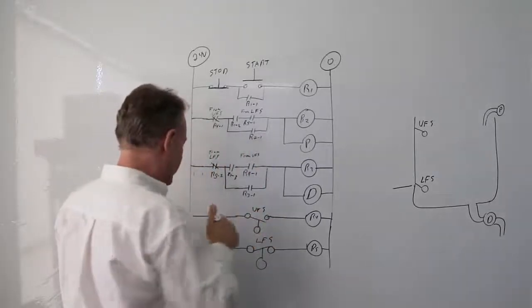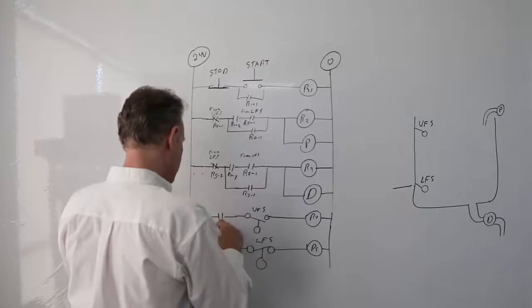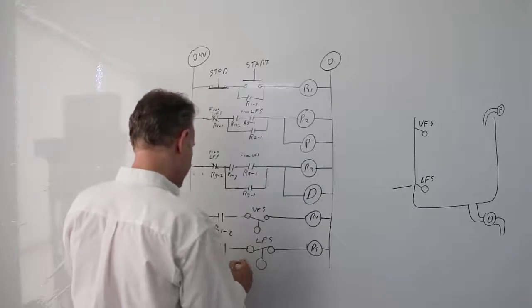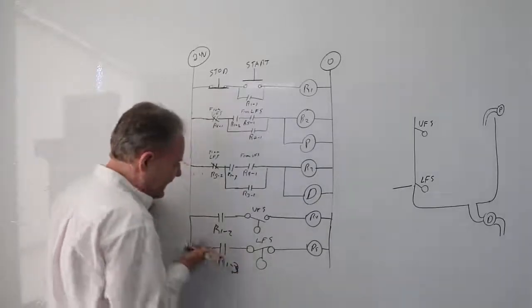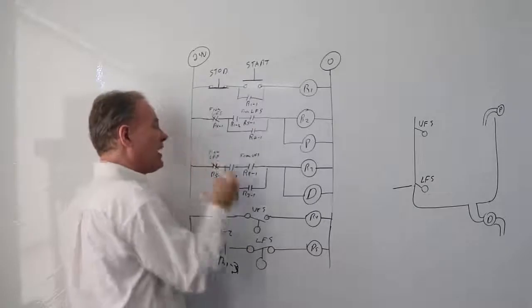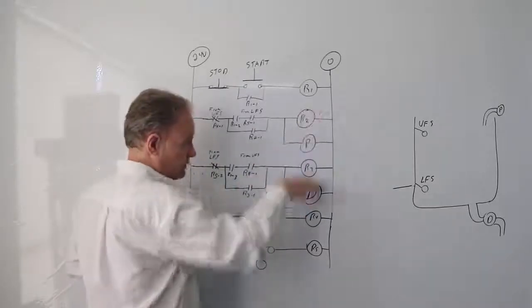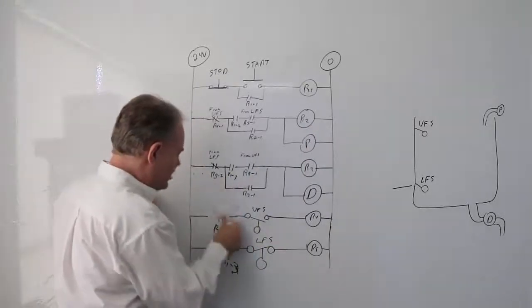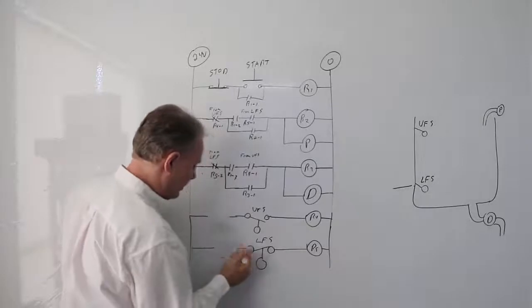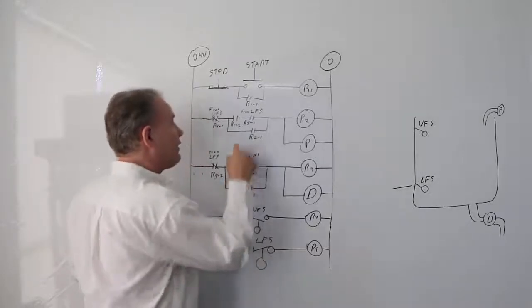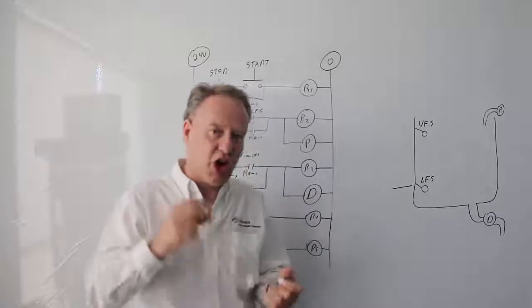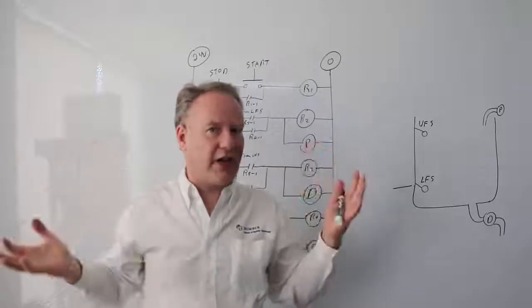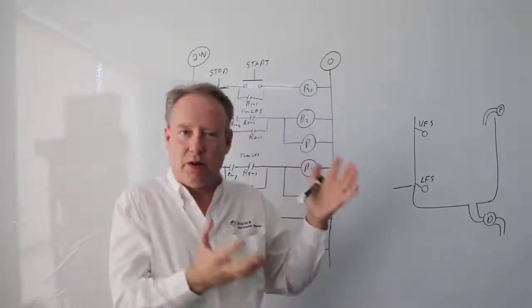So I can't actually just do this. R1-2, R1-3. Whoa. I can't do that, because I need these things to terminate the drain when it's empty and terminate the pump when it's full. So I'm going to put the stop contact in here and in here, because I want to target where my signal from whatever action is actually doing what it is that I want to shut off.